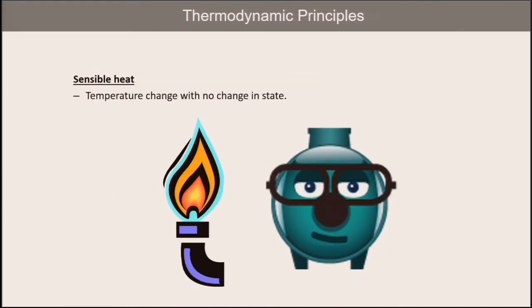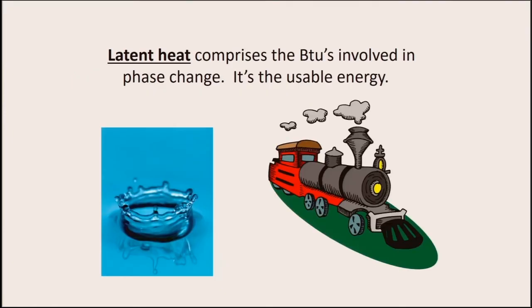This leads us to the types of heat generated in a boiler — there are two of them. The first is called sensible heat: this is the heat the burner supplies which goes into the boiler water to elevate its temperature, but it remains as a liquid — there is no change in state. This is different from the second form of heat, which we refer to as latent heat or latent energy. This form of energy comes into play once the water has reached saturation, meaning it can no longer take any more sensible BTUs or it will experience a phase change going from a liquid to a gas or steam. Steam is a gas and cannot be seen. The heat energy added at this point of saturation is called latent energy.